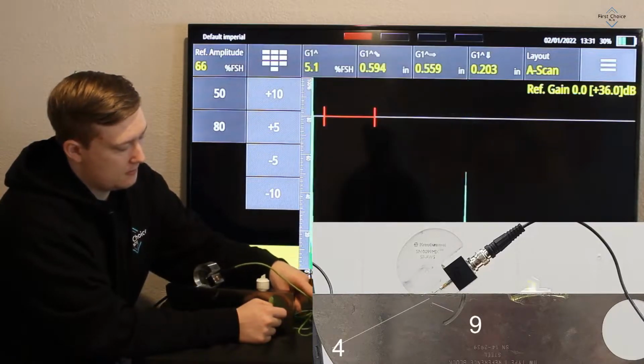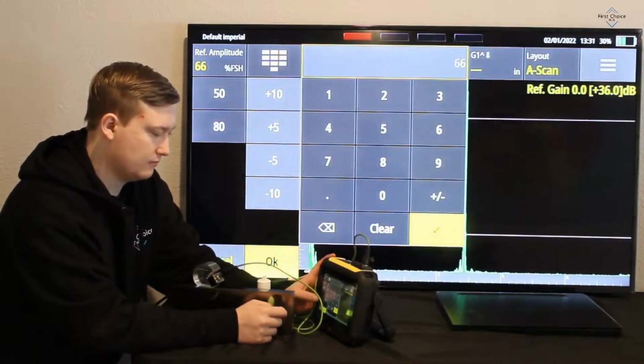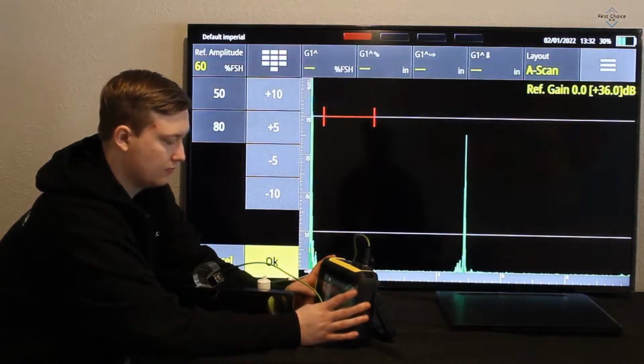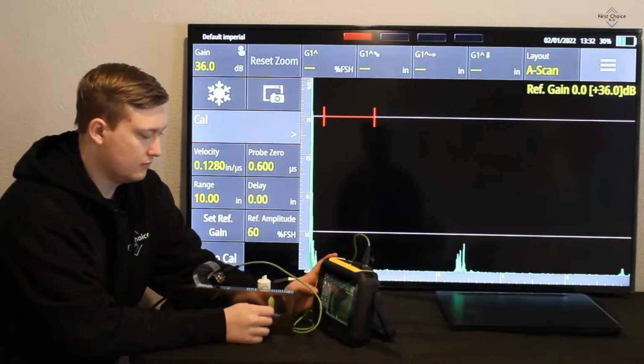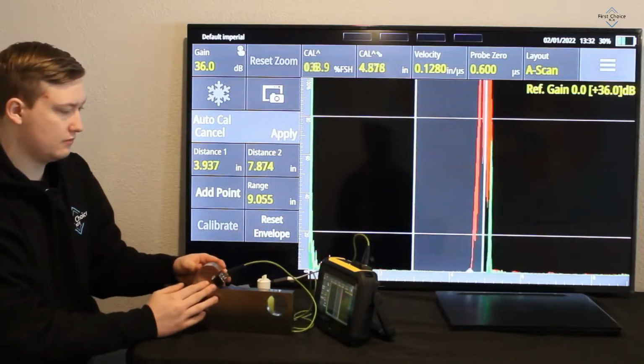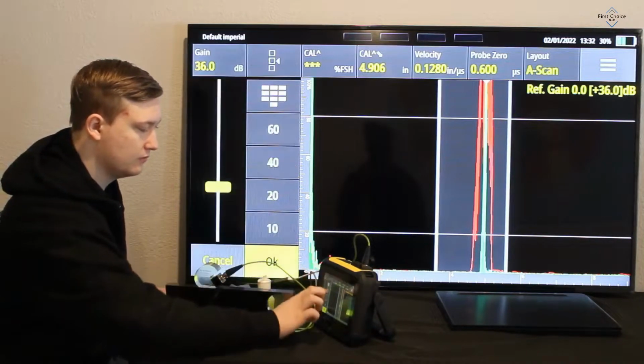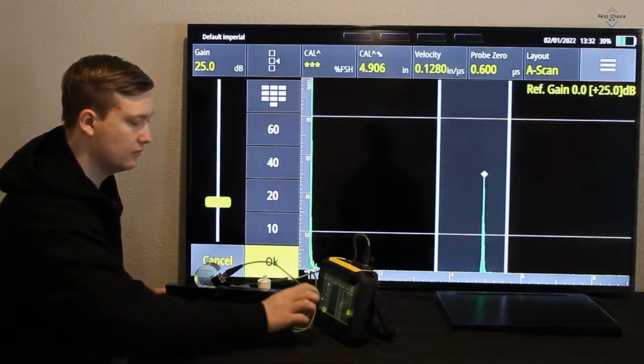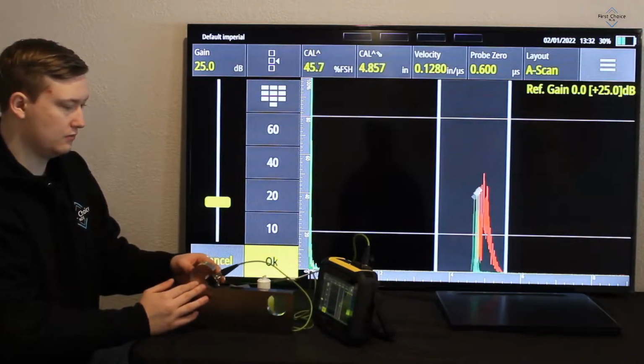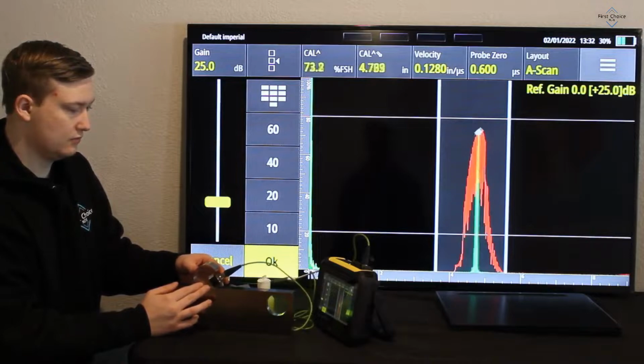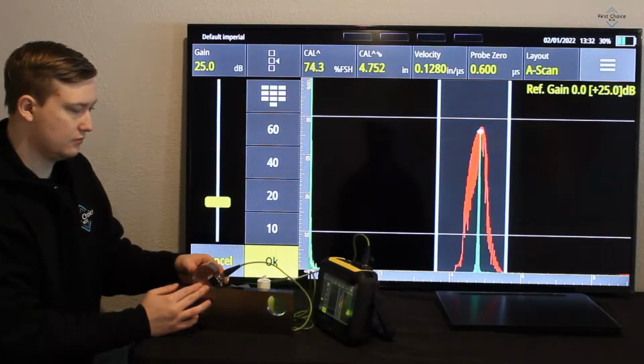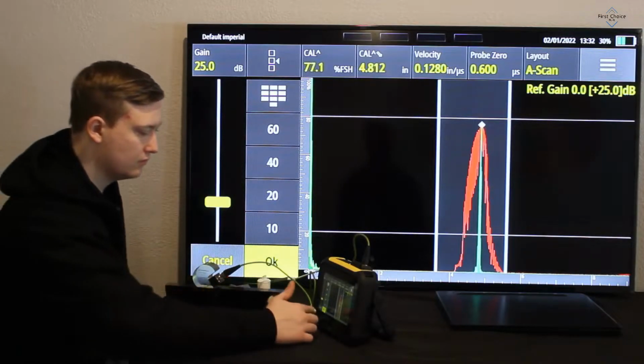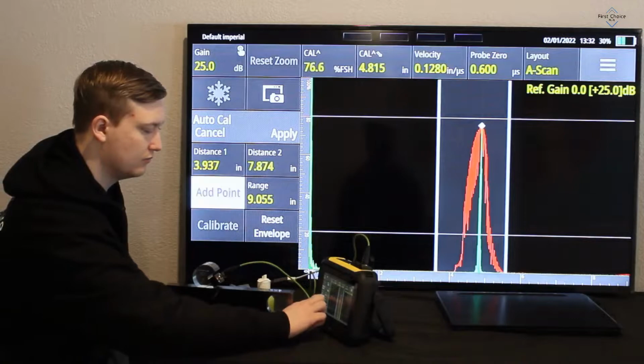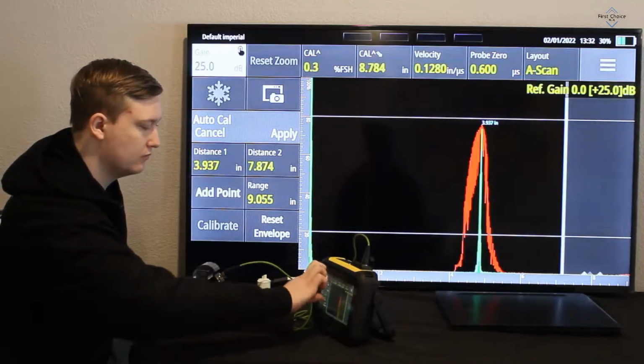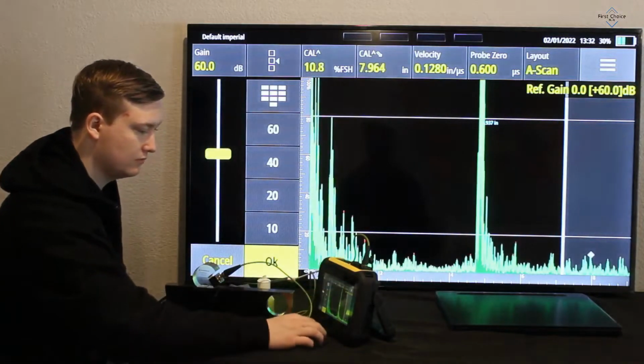I am going to put 60% for my reference screen height, because that is the percent I prefer. So now I have it at 60. So now I go ahead and I press AutoCal. So right now, I am focusing on the 4-inch reflector. And right now I'm just peaking it out. The envelope is automatically on, so you know exactly where the peak is.